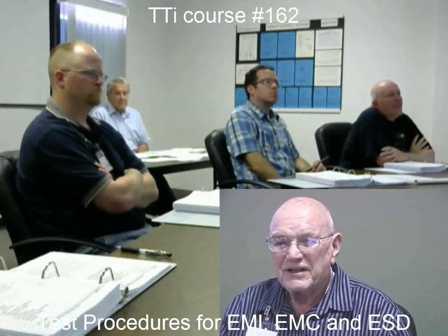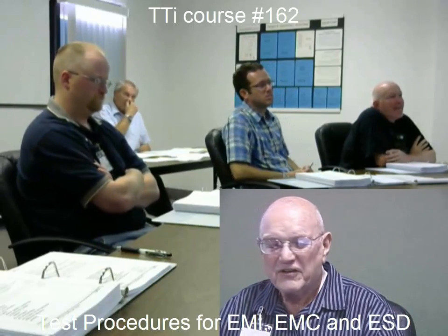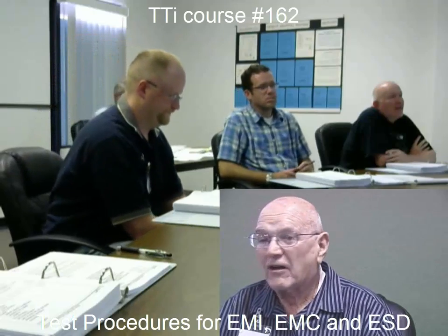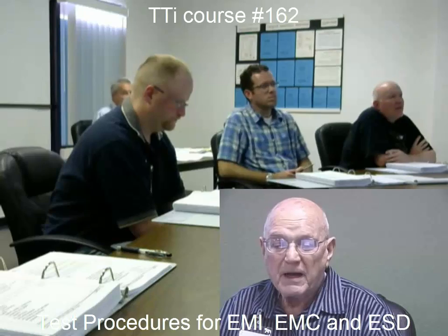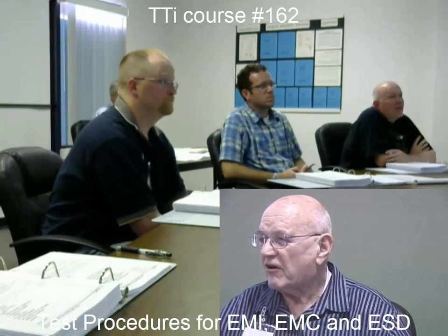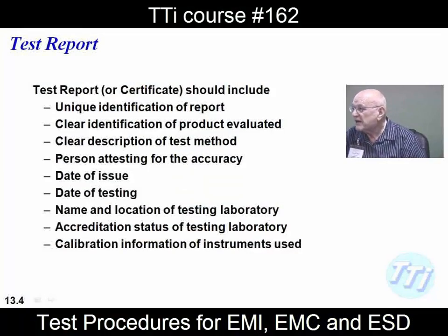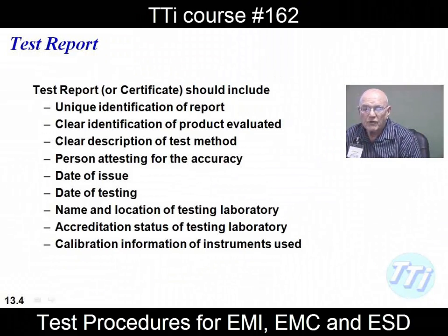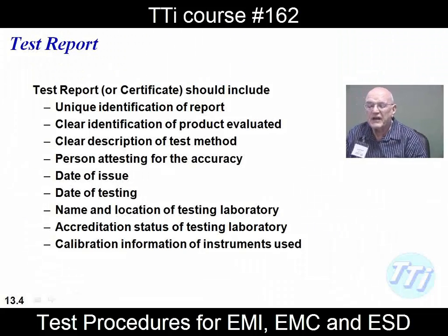Remember uncertainty. It's hard to make this transition. You might even well see the term accuracy used a lot in a lot of your documents. In reality, it's really uncertainty involved. So this is the guy that guarantees everything's with this accuracy, and you do report what the accuracy is, or the uncertainty with respect to each of the devices you have there. Because if you don't have that information, you can never come up with the proper uncertainty for the complete test.